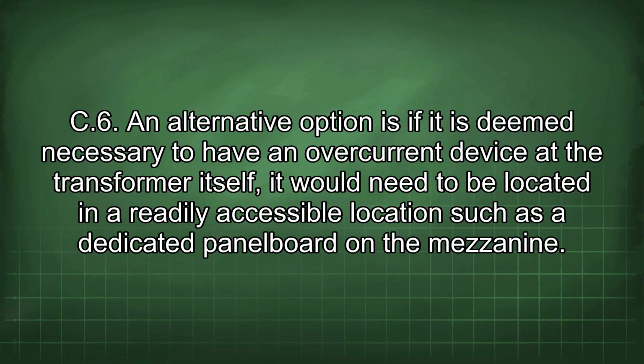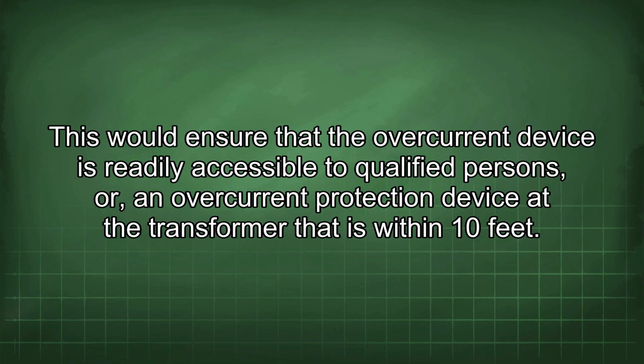240.21(C)(6). An alternative option, if it is deemed necessary to have an overcurrent device at the transformer itself, it would need to be located in a readily accessible location such as a dedicated panel board in the mezzanine. This would ensure that the overcurrent device is readily accessible to qualified persons, or an overcurrent protection device at the transformer that is within 10 feet.